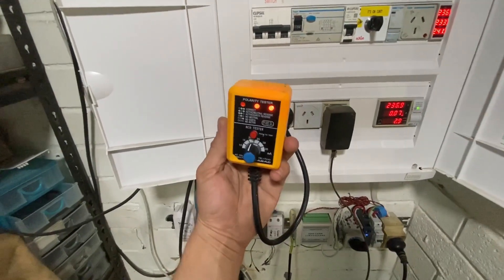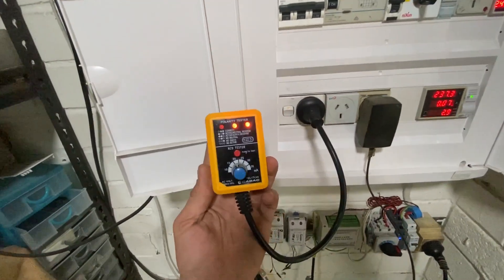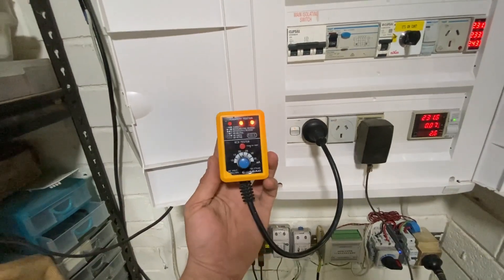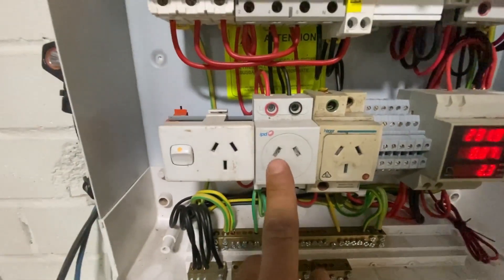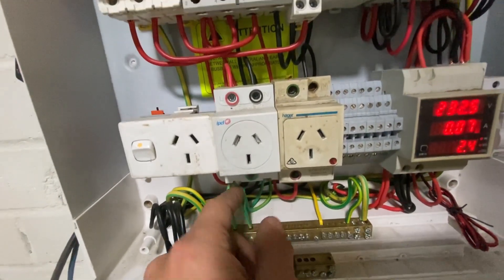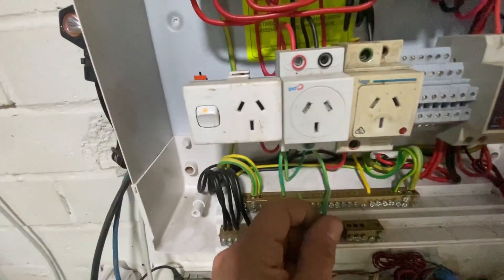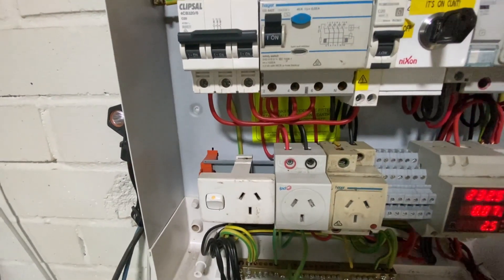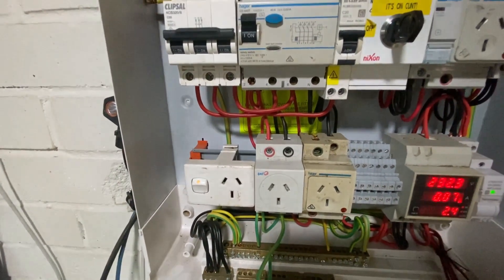I actually want to show you what happens when you don't do your earth continuity properly. I'm just going to do a transposition between neutral and earth. I'm going to rip this board apart and show you the process. I'll just use this third outlet because I've got a bit of length here. Let's destroy all the neatness just for the sake of a video, and transpose those conductors to show you exactly what it says on the meter.